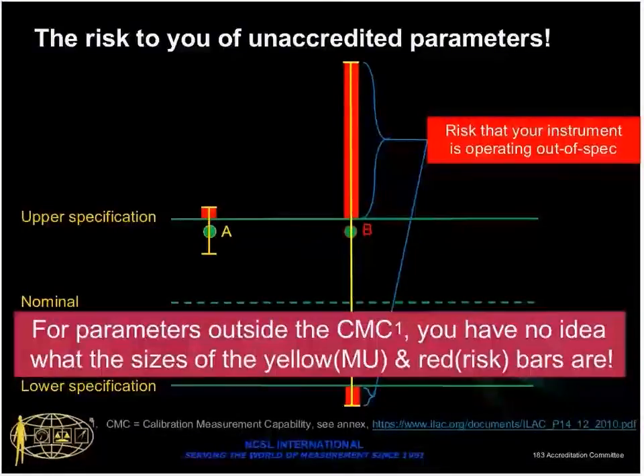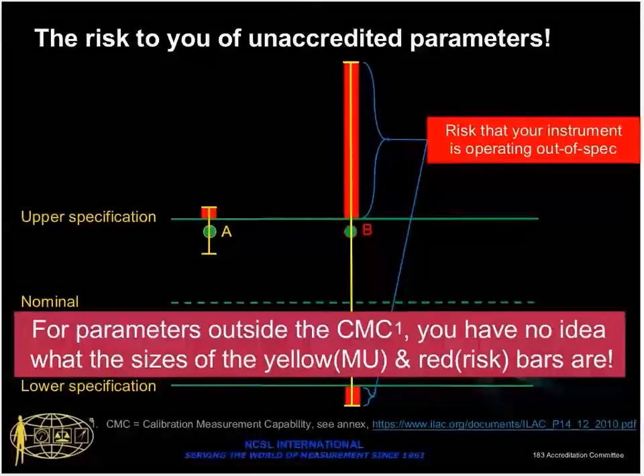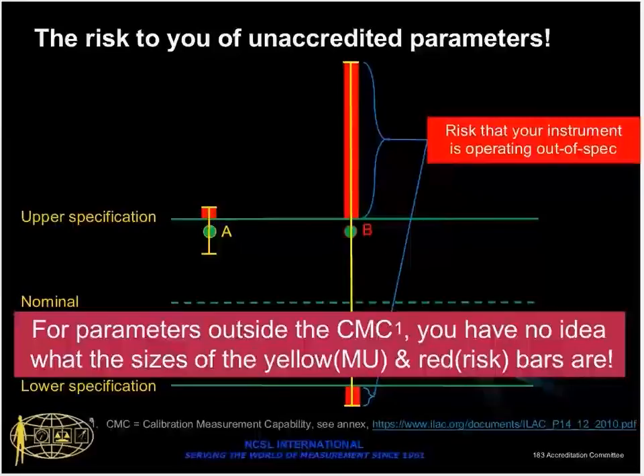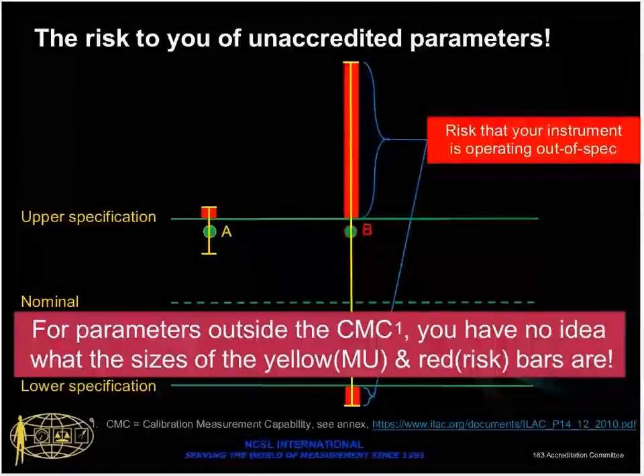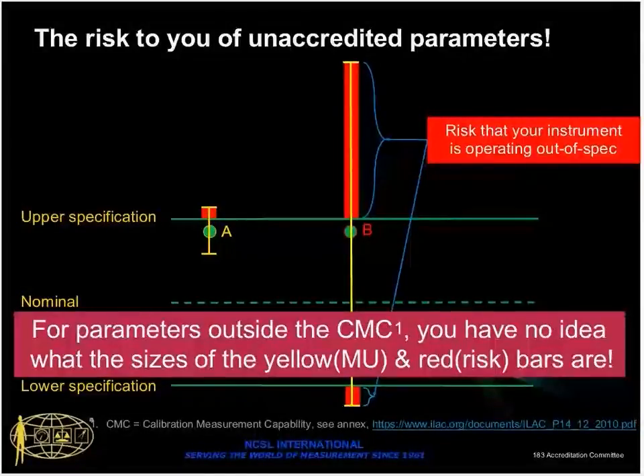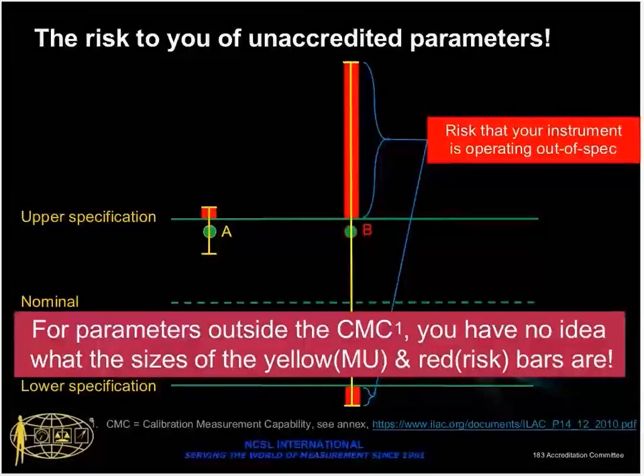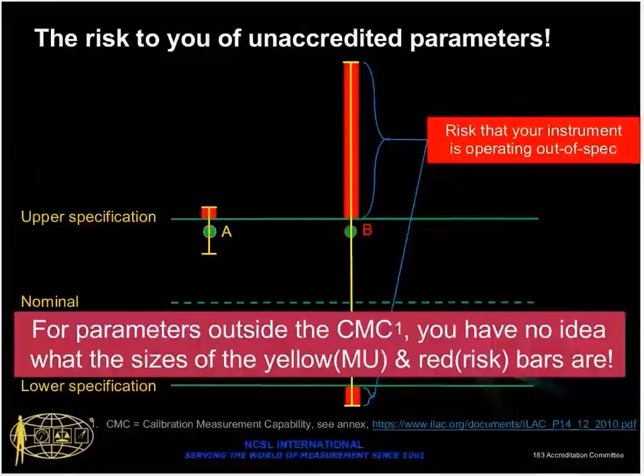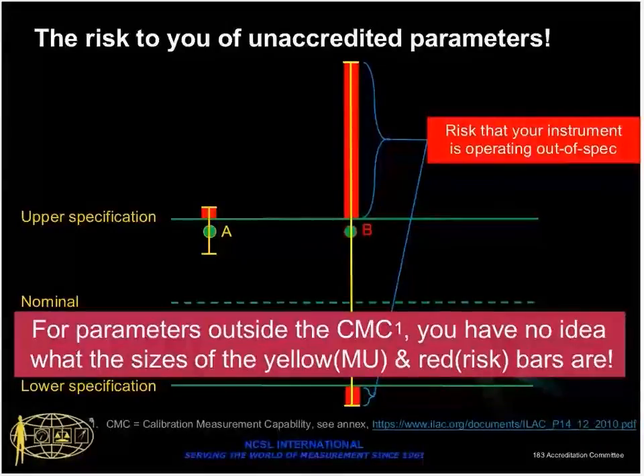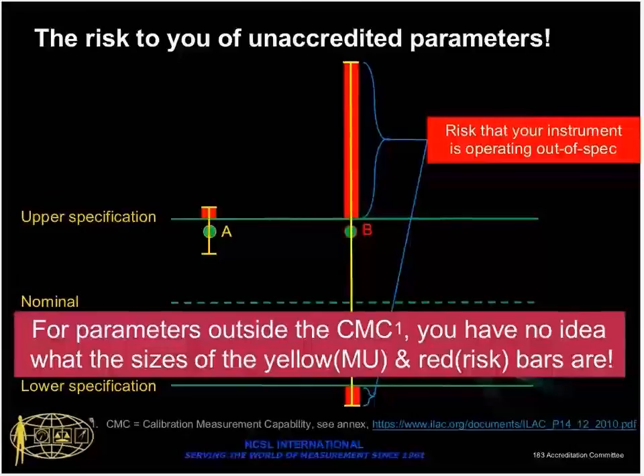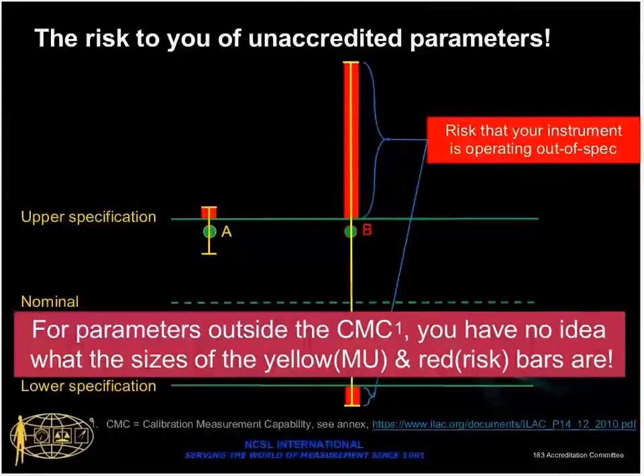Now, why are we telling you this with respect to accreditation? Well, the reason that I tell you about this is the following. In my experience, I have seen multiple cases where calibration labs offer to do work in areas where they are not accredited, and they are not listing it in their calibration measurement capability, so officially the only thing you know is that you don't know what their best measurement capability is. But unofficially, in my experience, oftentimes what that means is that they're using older instruments.